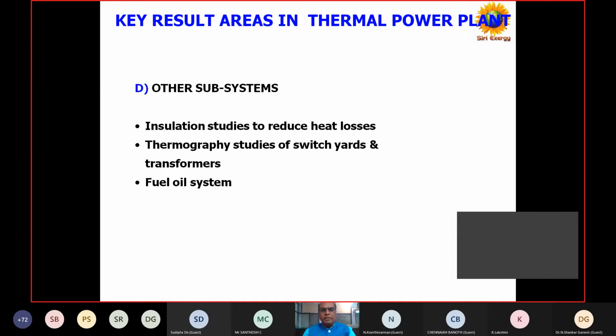Those we also do. Then we also do transformer thermography, even for transformers of the switchyard, because for transmission there will be hot spots in the distribution. There may be a 220 kV switchyard inside the plant. There again, there can be a hotspot, because with the naked eye you can't see it. Those things we also carry out as part of the scope of work, if it is there. Then there is the fuel oil system, because though we talk about coal handling, there is fuel oil. Fuel oil is required whenever you want to start the boiler, because we can't start with coal.